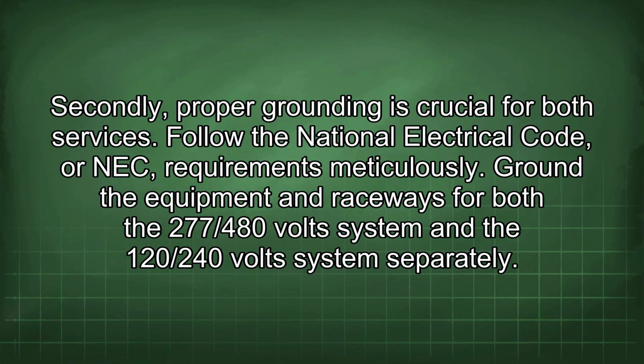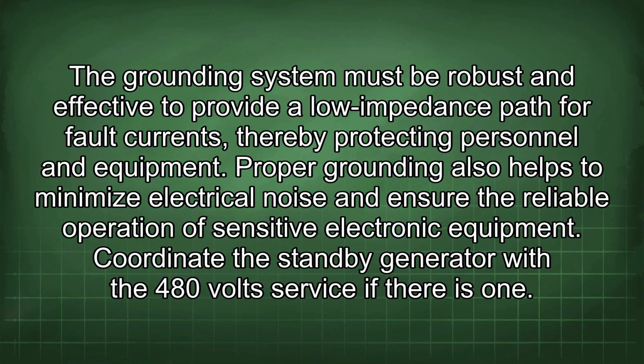Secondly, proper grounding is crucial for both services. Follow the National Electrical Code, or NEC, requirements meticulously. Ground the equipment and raceways for both the 277/480 volt system and the 120/240 volt system separately. The grounding system must be robust and effective to provide a low impedance path for fault currents, thereby protecting personnel and equipment. Proper grounding also helps to minimize electrical noise and ensure the reliable operation of sensitive electronic equipment.